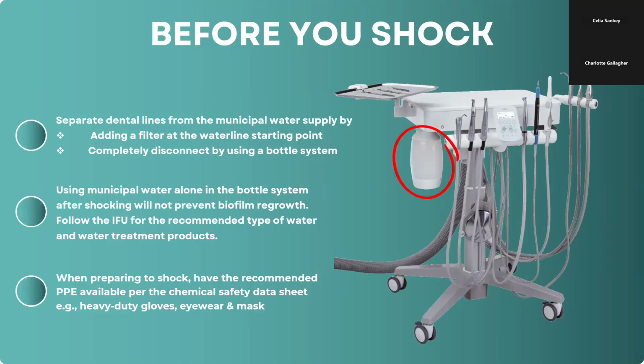Secondly, chemicals used to keep bacterial numbers down in municipal water supply may adversely interact with chemicals used to treat and maintain dental water. This separation of lines can be done with a filter at the dental water line starting points, or entirely disconnecting the dental unit water lines from municipal water supply and using a refillable bottle system shown here. But be aware that filling the bottle with municipal water alone after shocking will not prevent biofilm regrowth, because even municipal water at its best still contains bacteria that will reform biofilm. So you should follow manufacturer's instructions on the recommended type of water, water treatment, and preventative maintenance waterline products.